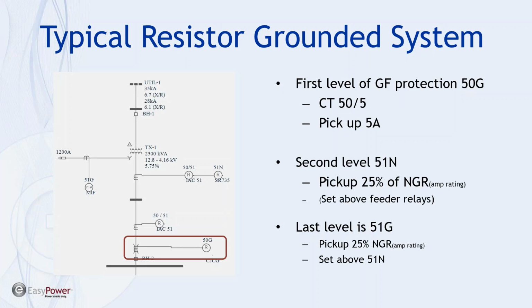And the second level of protection is provided by the 51N function, which we'll see initially picks up at 25% of the ampacity rating of our ground system, and then we want to coordinate it with the feeder relays below. And then thirdly, we'll utilize as our last line of defense the current in the ground leg going to the high resistance at the transformer.